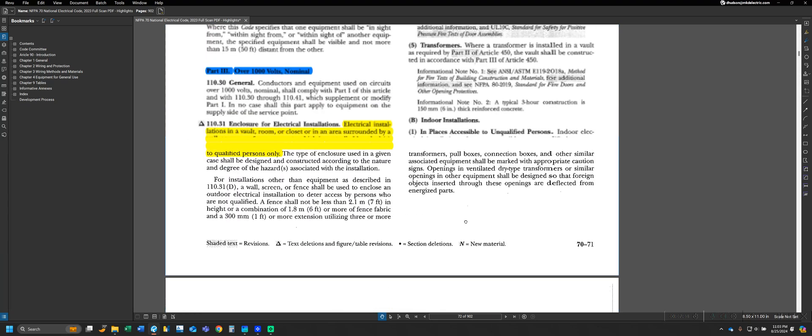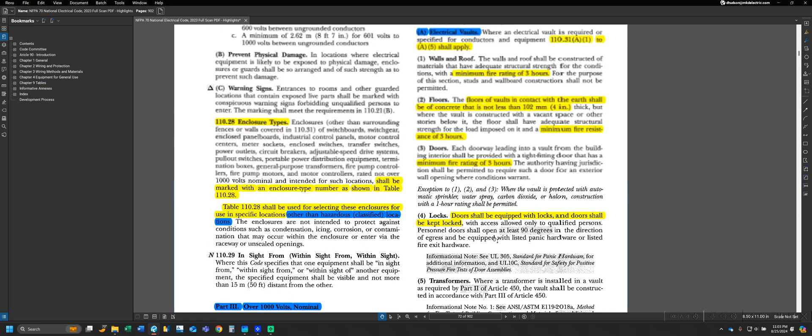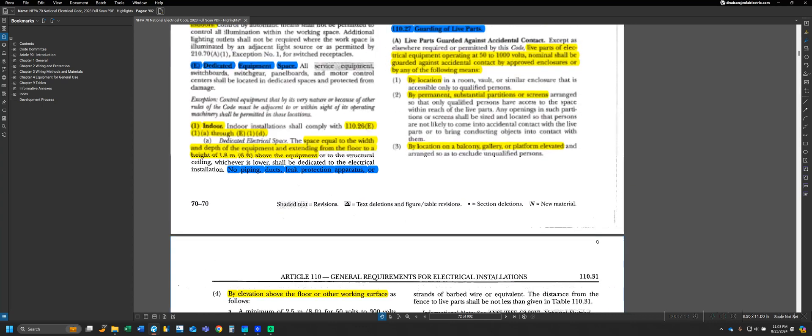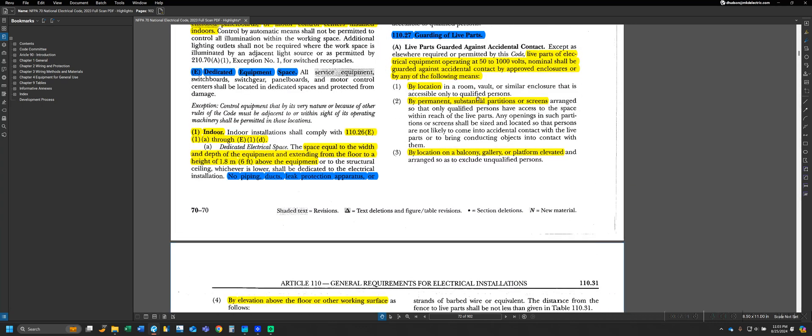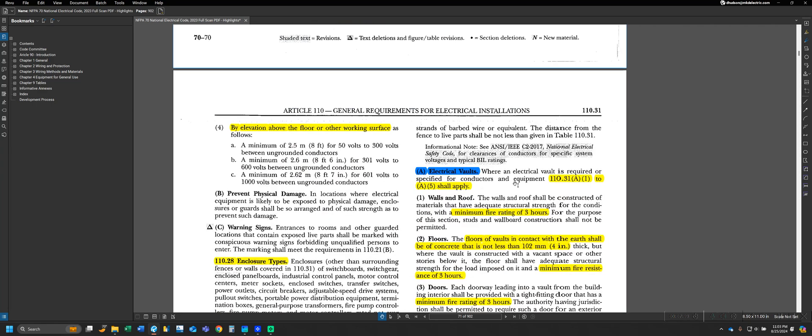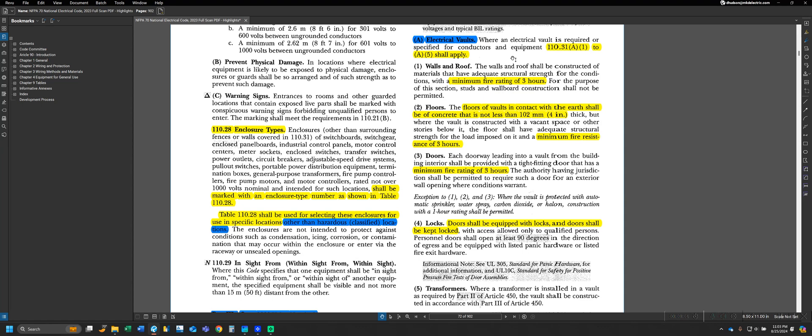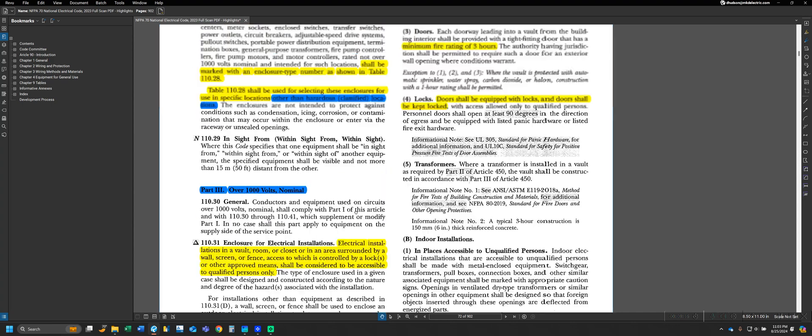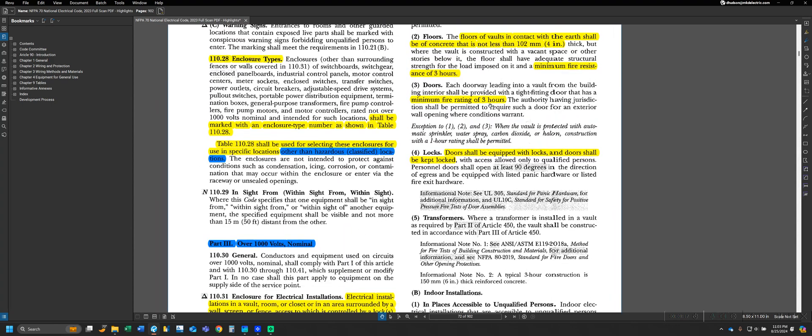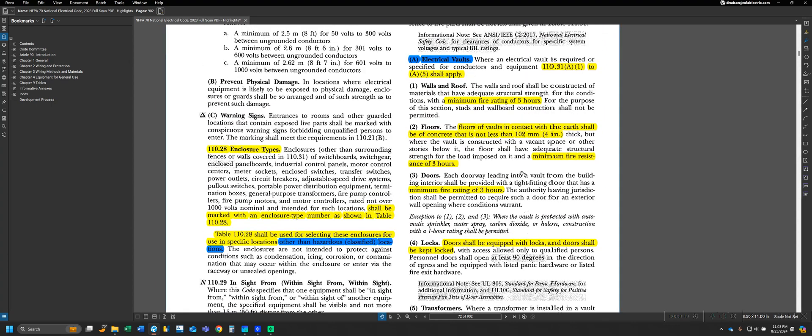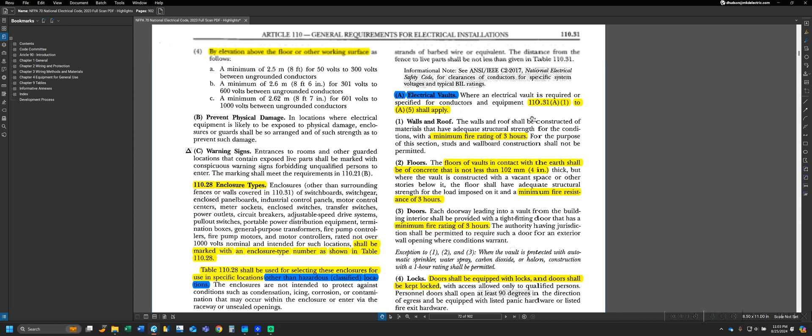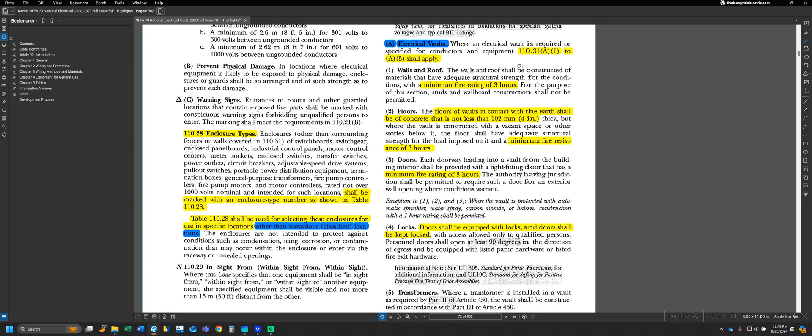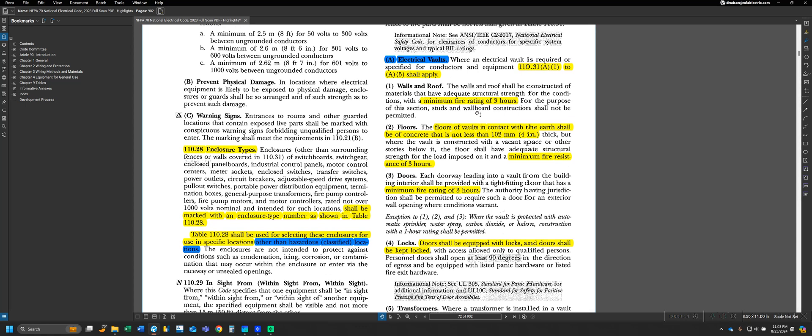Aside from enclosures, one of the things that we previously referenced are vaults or other similar enclosures. In addition to regular enclosures, the NEC does give us some provisions for vaults that we have to meet as well and consider. This does cross over into part three for over 1,000 volts nominal that we're going to be looking at. However, these are general requirements for vaults themselves to consider. We're just going to briefly go over those so we can see part A for electrical vaults, which is broken down from 110.31A1 to A5. Generally speaking, a level of fire rating and fire prevention is what the code is going to be looking for, and that's kind of reflected in these areas.